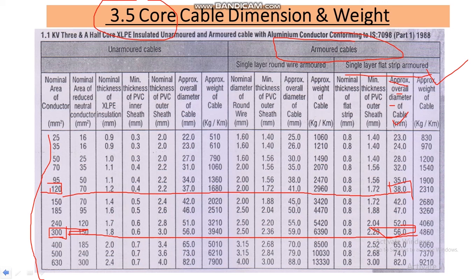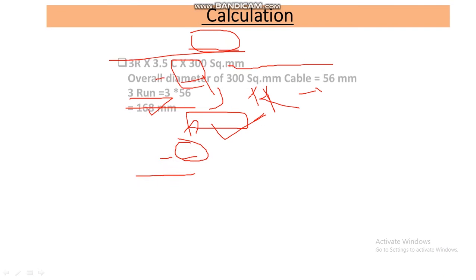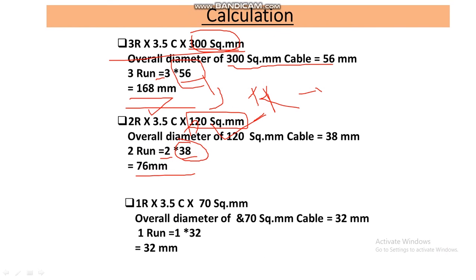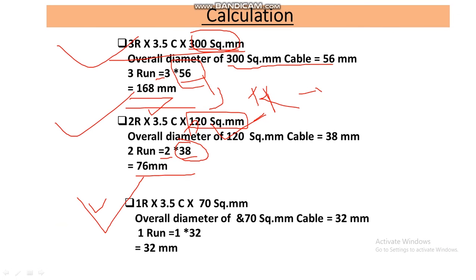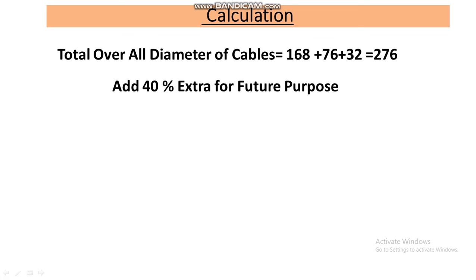Similarly, for one run of 3.5-core 70mm² cable, from the cable catalog the diameter for 70mm² is 32mm. So the overall diameter for one run is 32mm. Now summing all the diameters: 168mm + 76mm + 32mm = 276mm total overall diameter.